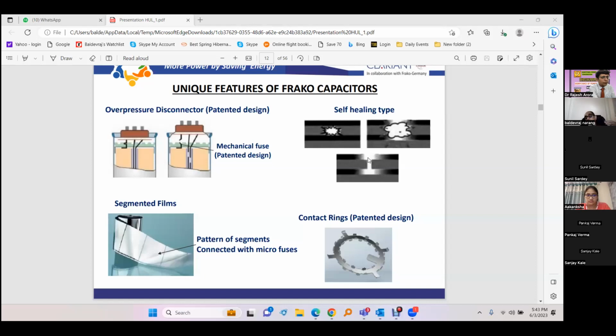And an APP capacitor, on the contrary, has no self-protection, and when it fails in a short circuit mode, it remains connected in the system as a thick wire. So what is happening is, today we have harmonics, as most of the loads are non-linear loads. We are having harmonics and we are having resonance conditions. And during resonance, it is like a short circuit. And the capacitor is the item which takes the maximum burden of this resonance condition, the short circuit condition.